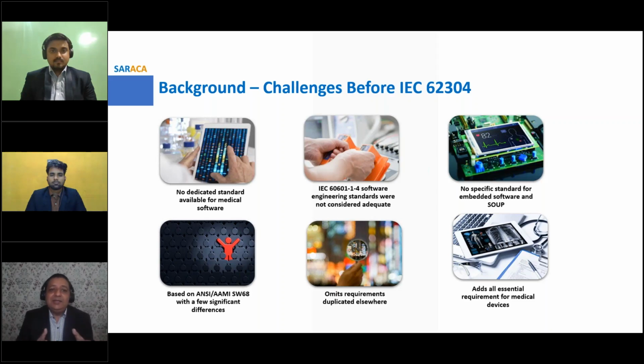Previously there was no dedicated standard available for medical software. There were ANSI standards, there were AAMI standards, there was 60601-1-4 with some elements of medical software, but there was not a dedicated software standard for medical devices. There was nothing special for embedded software and SOUP. We'll talk about SOUP in the subsequent slides. Now IEC 62304 is based on AAMI SW68, which was the earlier standard used by some medical device manufacturers. It omits a lot of requirements. So there was a lot of mix and match with ISO 13485.